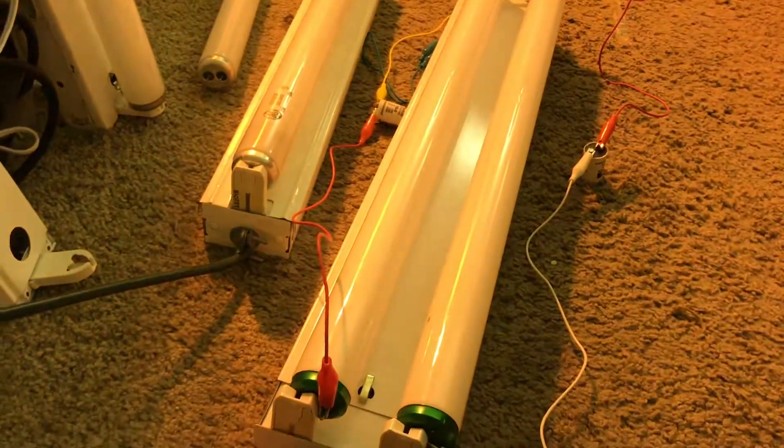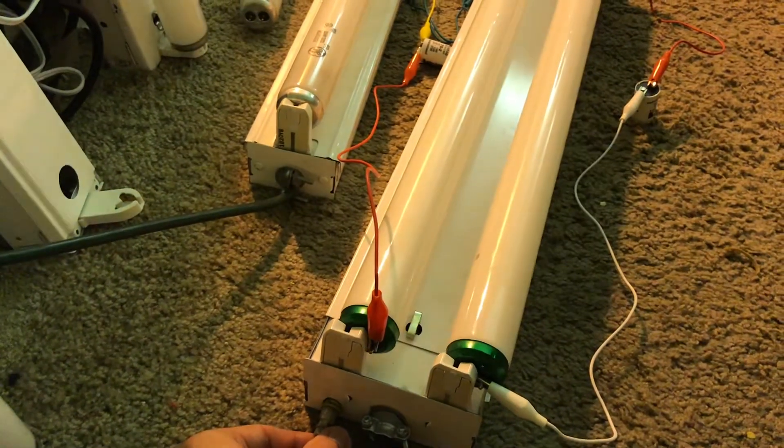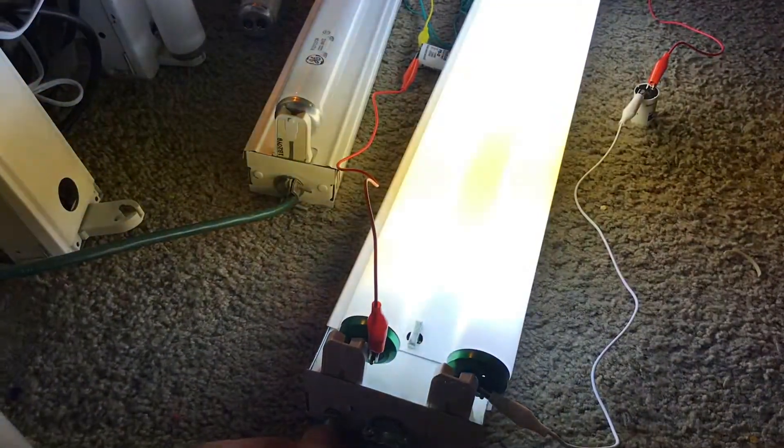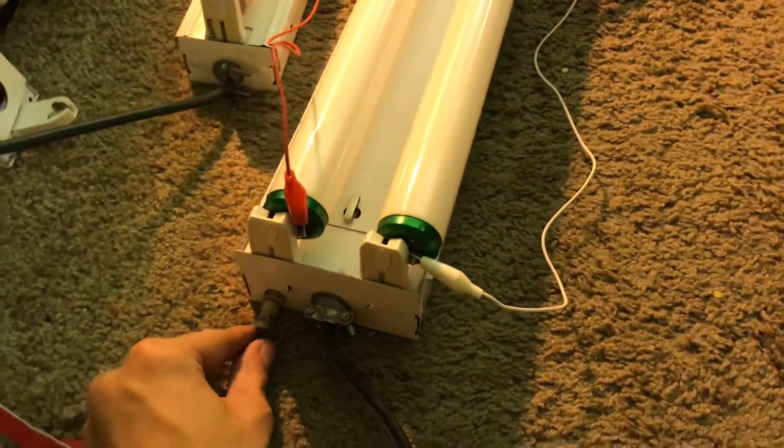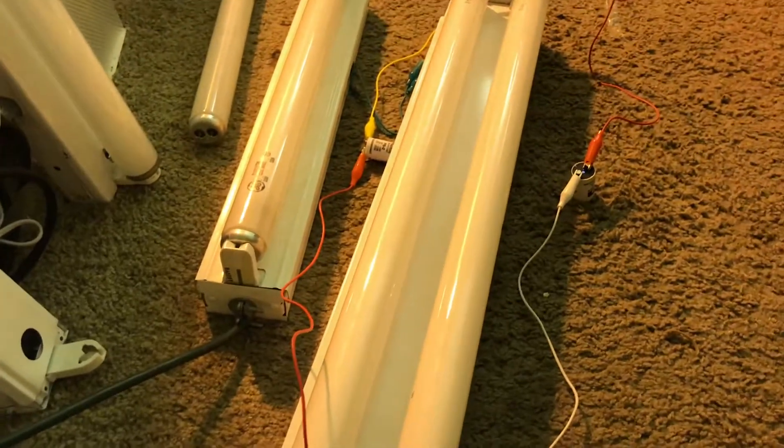Yep, pretty much behaves like those old two lamp preheat ballasts from the 40s. This is a high power factor magnetic rapid start ballast. These are F20 T12s.